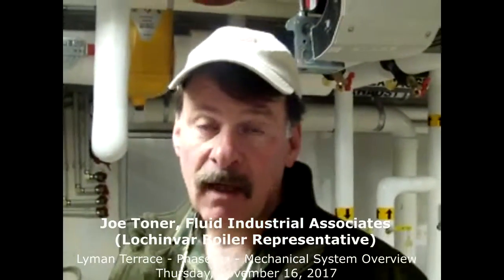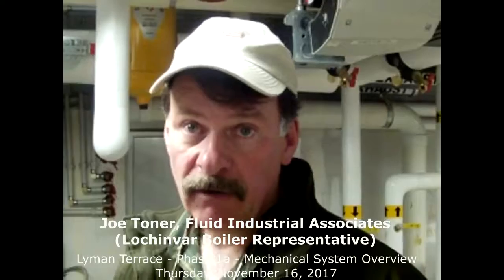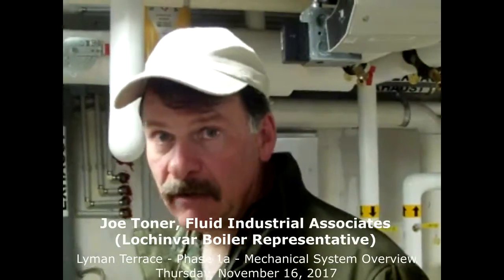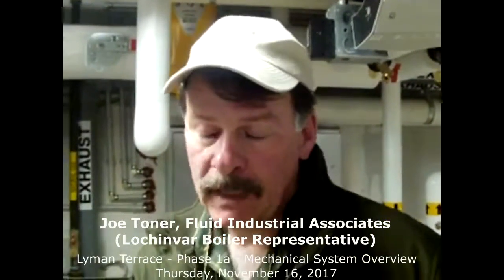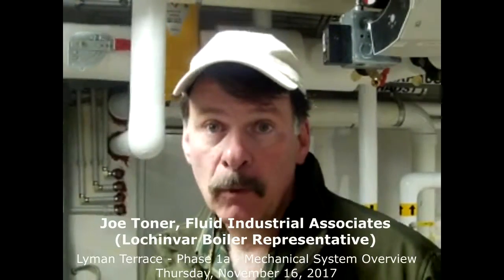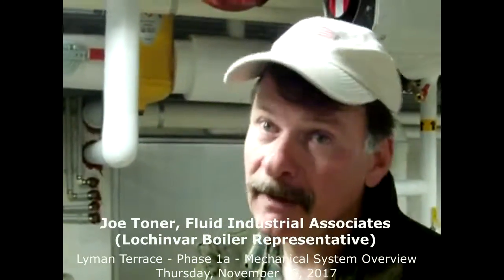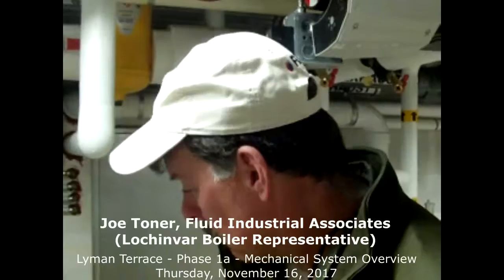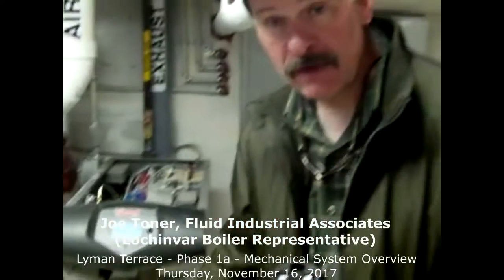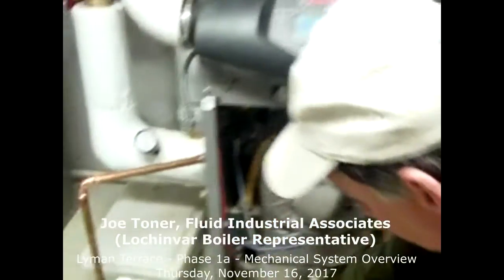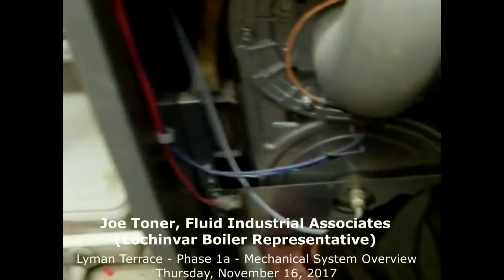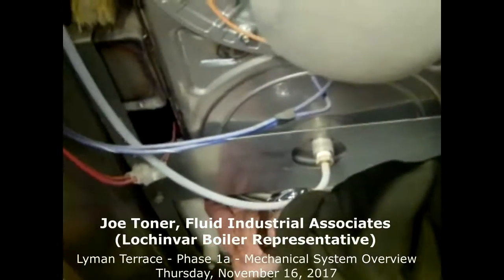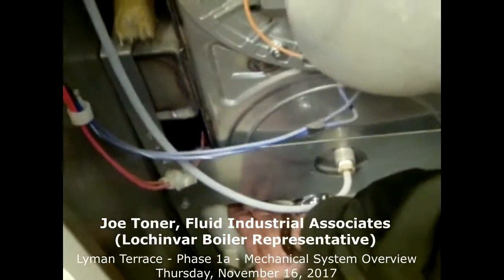So if it never gets done and there's a failure with the heat exchanger, Lochinvar tests their heat exchangers, and if we can't provide evidence that they've been serviced annually, then they're not going to honor the warranty. So that's kind of important. The other thing to note is there's a condensate trap right here. Very easy to disassemble and just inspect to see if any sludge or buildup has accumulated in it.